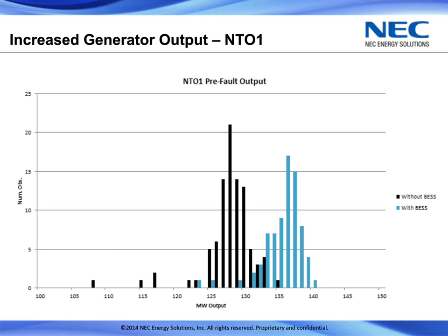NTO1 is one of the coal-fired generating plants being supported by the BESS, the Battery Energy Storage System, labeled BESS in this graph. Without the BESS, prior to its installation, the average output was somewhere between 125 and 130 megawatts, shown in black.